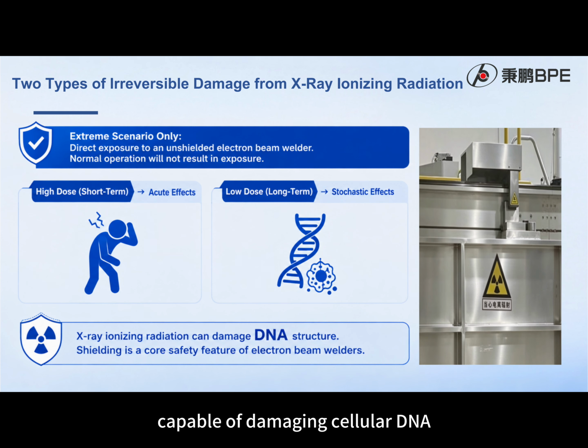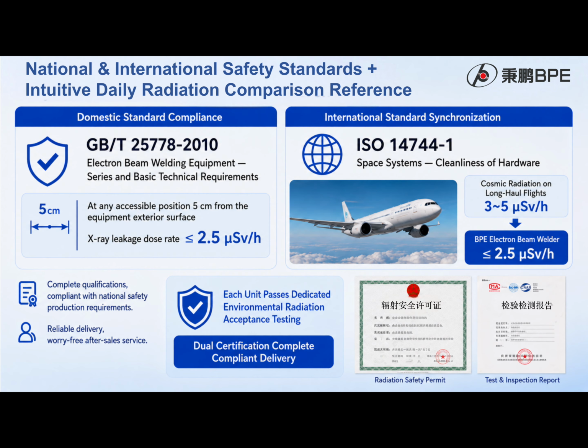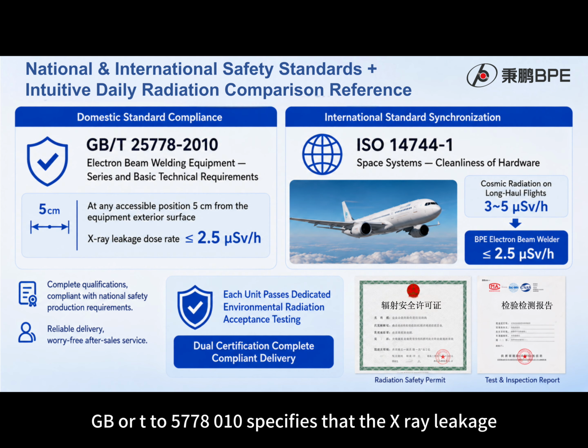National and international standards establish mandatory limits for X-ray leakage from industrial electron beam welding equipment. GB/T 25778-2010 specifies that the X-ray leakage dose rate at any accessible position 5 cm from the equipment surface shall not exceed 2.5 μSv/h. For high-end aerospace manufacturing, ISO 14744-1 may also be used as an equipment acceptance reference.